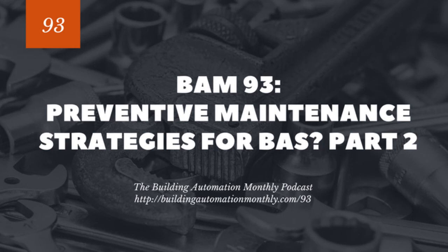All right, so let's recap these 16 preventative maintenance actions that we discussed. You've got backing up databases and tuning PI loops, calibrating sensors and verifying control device operations, adjusting schedules, clearing operator overrides, alarm management, and naming standards. That was all in the previous episode, episode 92. And in this episode, we went through maintaining set points, trend log reviews, network checks, and software updates. And when I say software updates, I mean patching, checking for unbound references, BACnet and duplicate network IDs, BBMDs, instance numbers, optimizing existing networks, COV versus internal trends, getting that all working well. Sequence verification, and why it's important to rely on that and not just verify a control device operation.